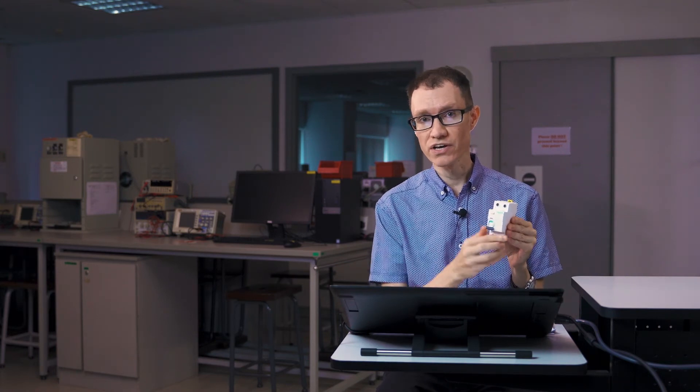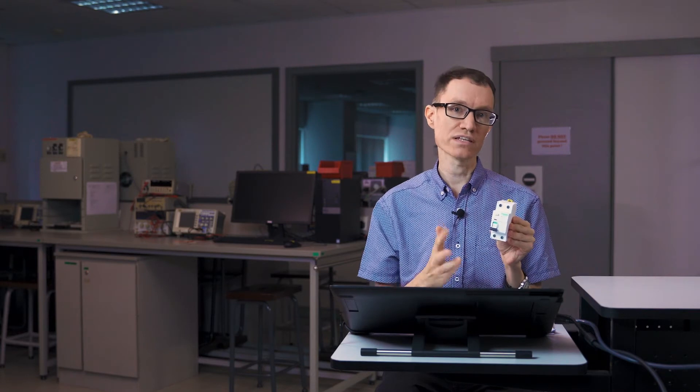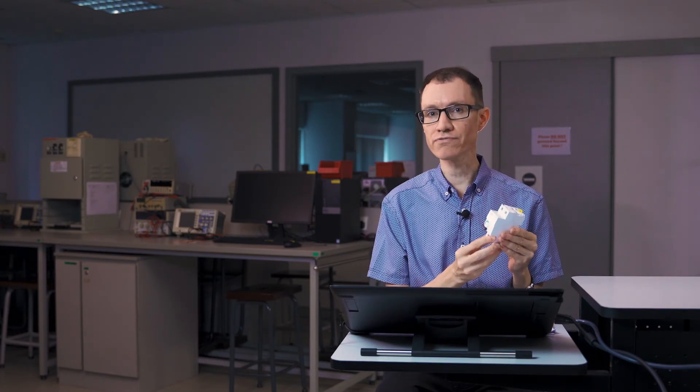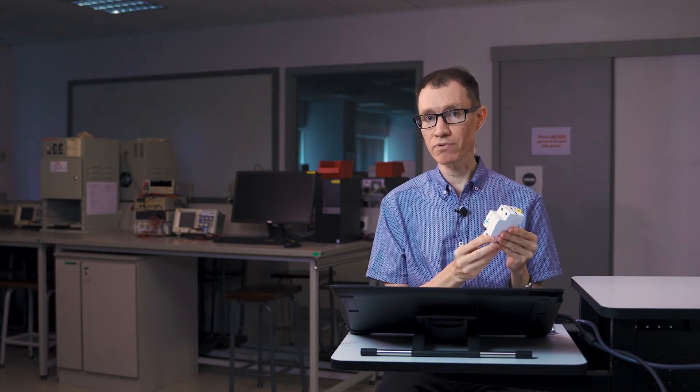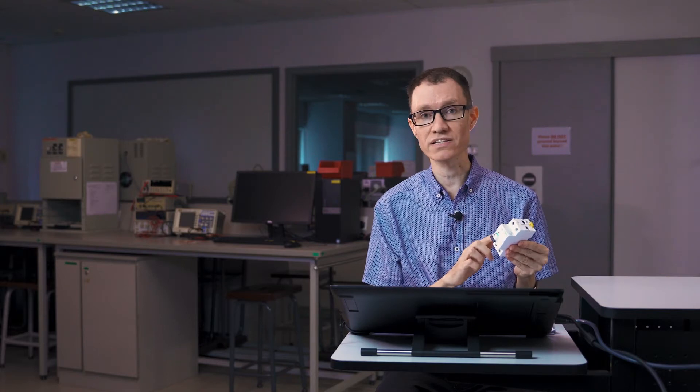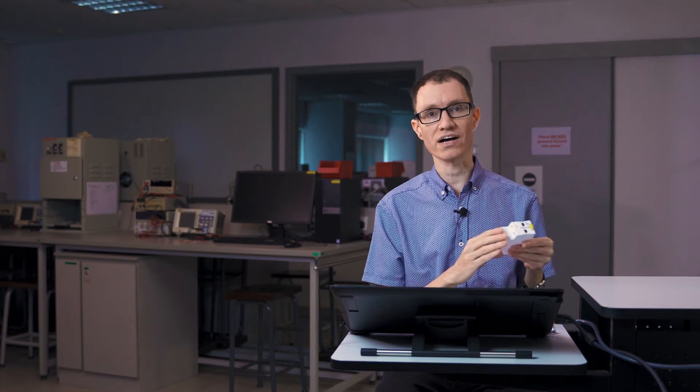What this device does is it monitors the amount of current going through the hot side and compares it to the amount of current coming back through the neutral. If the two differ by a preset amount, which is printed on the side of this circuit breaker, then it'll trip and break both the neutral and the hot connections simultaneously.